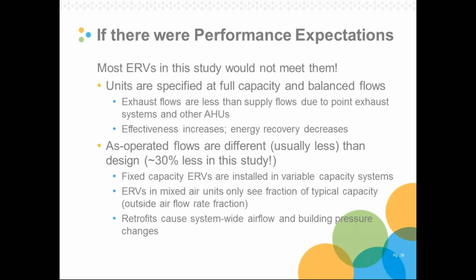Fixed capacity ERVs are installed in variable capacity systems. ERVs in mixed air units only see a fraction of the typical capacity. And then lastly, a lot of the units in the study were retrofit units, and retrofits caused system-wide airflow and building pressure changes that will affect supply and exhaust airflow rates.